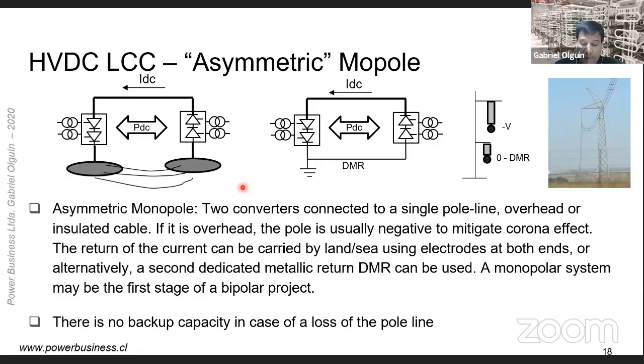The most basic configuration of an HVDC link is the monopolar link. In a monopolar link, two converters are connected to a single line, overhead or insulated cable. If it is overhead, the pole voltage is usually negative to mitigate corona effect. The DC current can be carried back to the rectifier by land or a dedicated metallic return. Some redundancy can be introduced in the converter station to increase reliability, but the main drawback of a monopolar link is that there is no backup for the transmission capacity in case of loss of a pole line.